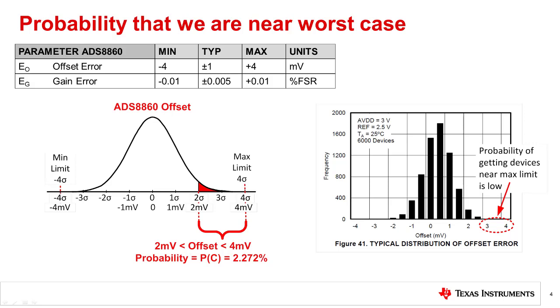From a statistical perspective, how likely is it that we find a device at the maximum limit? For this example, what is the probability that we get a device at exactly four millivolts? Since probability is equal to the area under the curve and the area under a single point is zero, technically the probability is zero. This isn't very helpful, so let's consider the probability that we are near the maximum limit. In this example, the probability that we are between two millivolts and four millivolts is 2.272%. This makes sense when you look at the measured histogram as you really can't see any bins in this region.